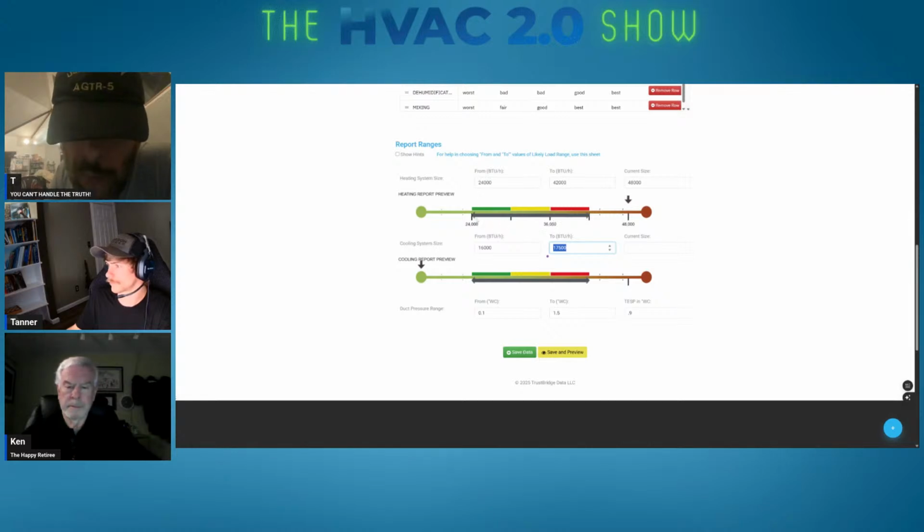And then when we show the static pressure limitation, it's going to be on the cooling side, so that people are encouraged to size the heat pumps to cooling. We really encourage people to size heat pumps to cooling, particularly if they're going to use 1 or 2 stage.